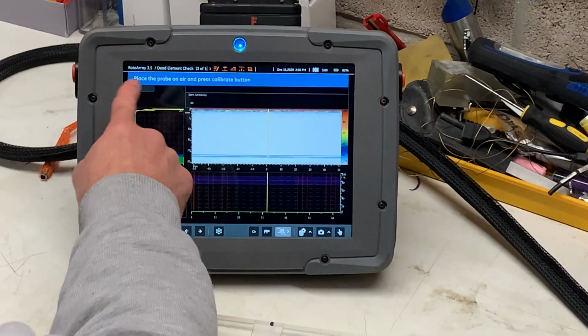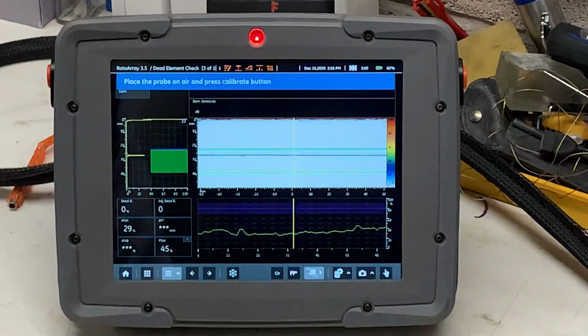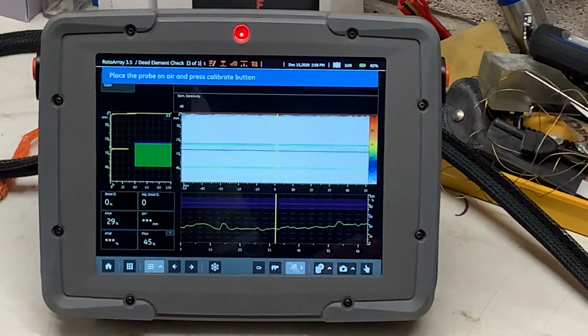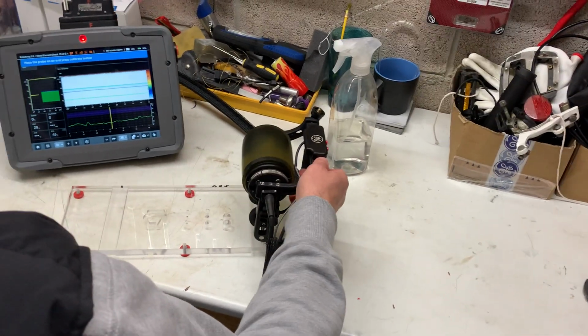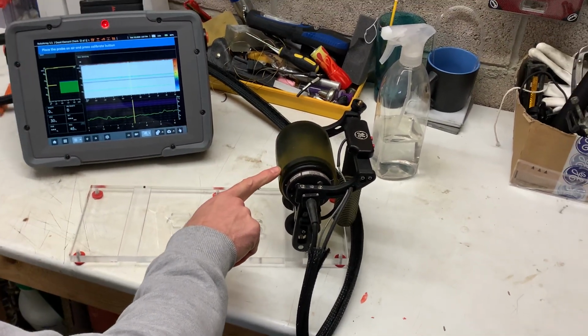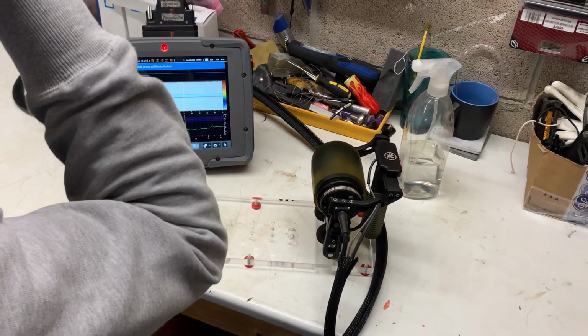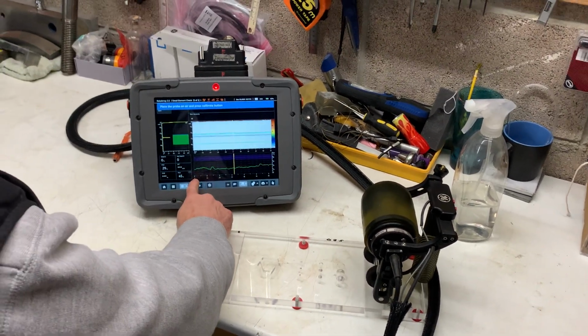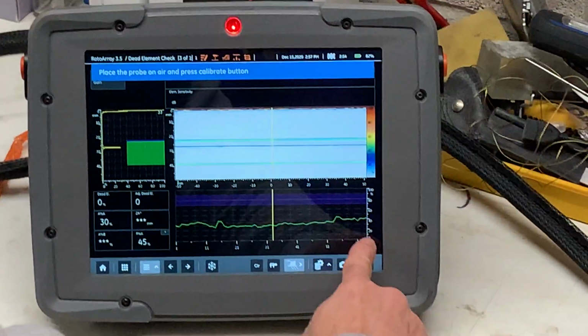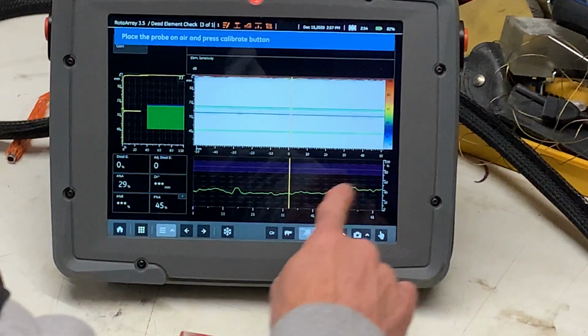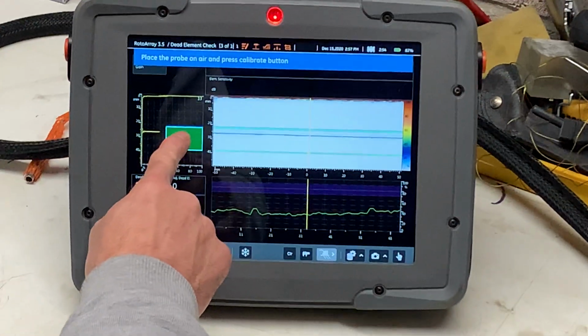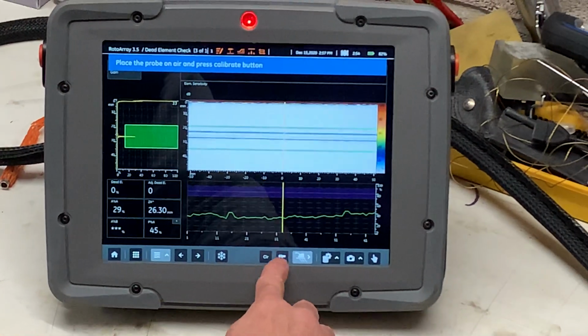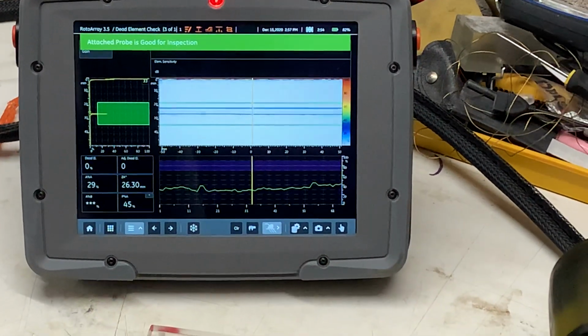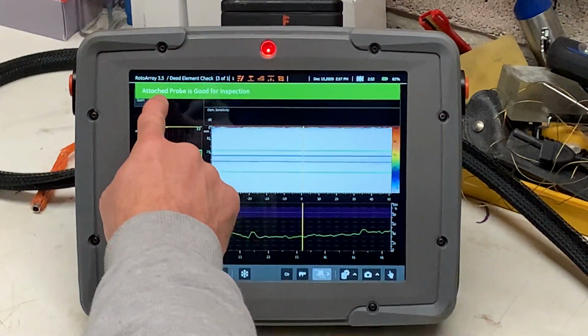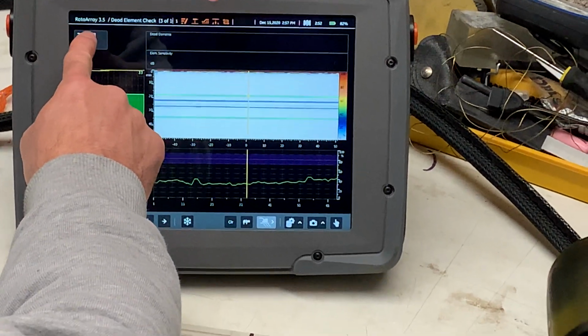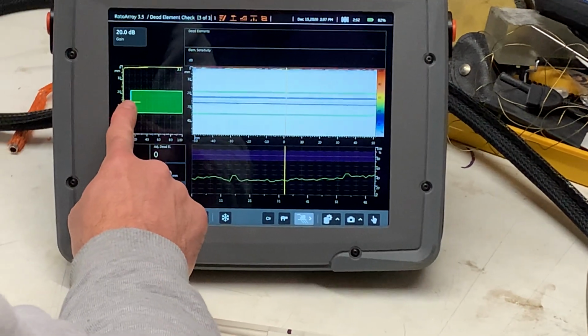So we move to the next page, and it tells you there, dead element check. Okay, so place the probe in the air and press calibrate. So I've got the probe standing up like this. And what it's using is the reflection off the inside of the tyre to check for any dead elements. So this is the output of our elements from 1 to 64, and you can see they're all kind of a similar output. And use it on the A scan. We just got to make sure that they're in the gate, and then this little vernier button is the calibrate. And it said attach probe is good for inspection. So when you do something correct, it goes green. When it's incorrect, it's red.